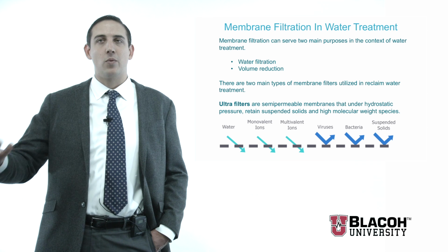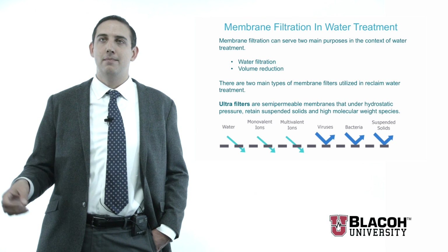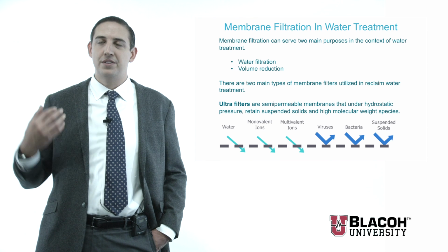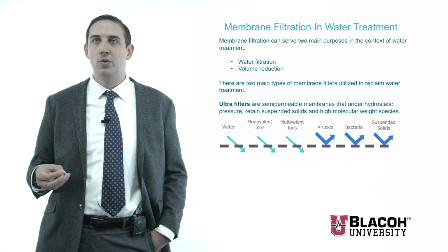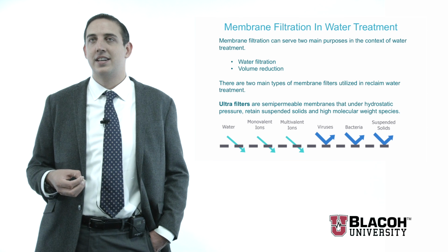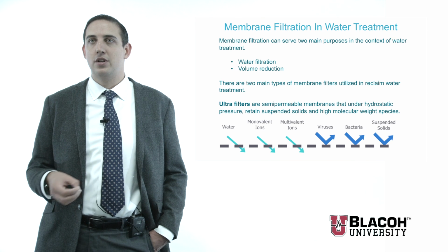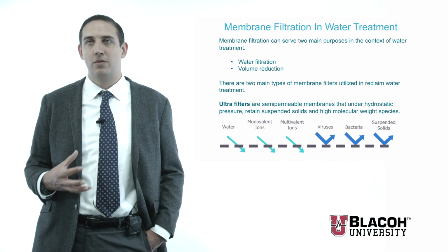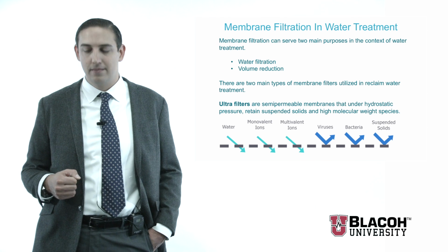For example, down in Washington, D.C., the Potomac River basically floods out that entire area. Any building you put in, you're displacing a lot of water in those cases, and you need membranes to help remove that very high ionic content. It's also the only type of filter which can remove discoloration. There's no other means of removing discoloration from the water without going to a membrane level treatment system.